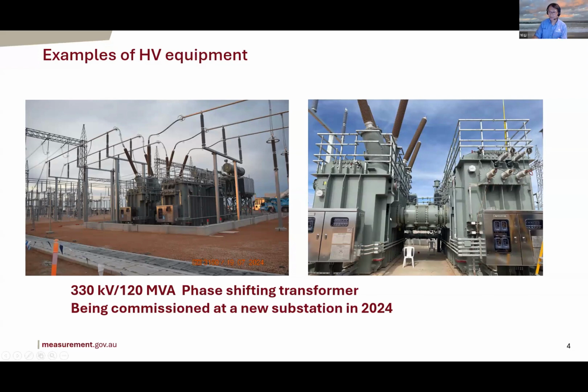And this is a close-up. It's a big apparatus or equipment. This particular one is probably 300 tons, but there are much bigger ones. One single phase 1200 kV transformer is about 800 tons. We are focusing on the insulation of these devices, such as the transformer. You have internal insulation, which is oil and paper in this particular one, and the external insulation, the bushings for connection to the electricity grid, which are polymers. So the testing we are talking about today, or in high voltage generally, is really just for testing the integrity of this electrical insulation. That's a very important point. We need to remember that.